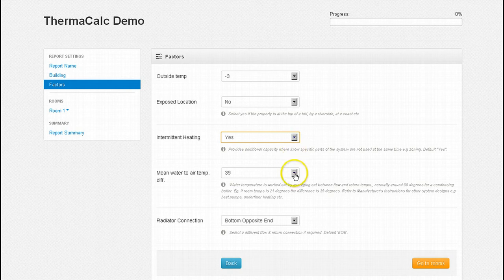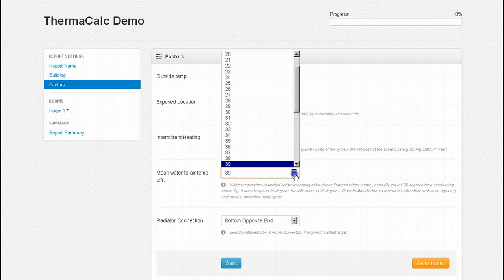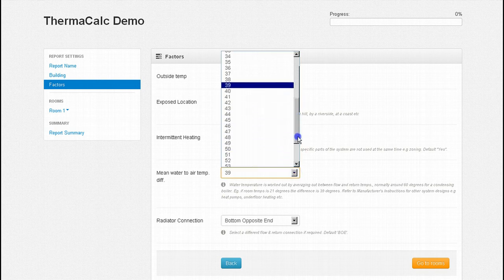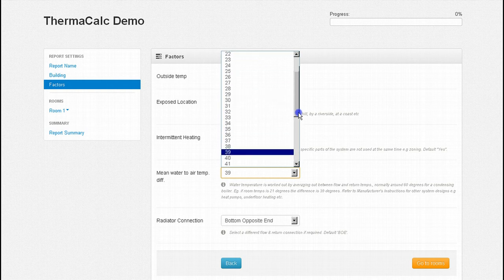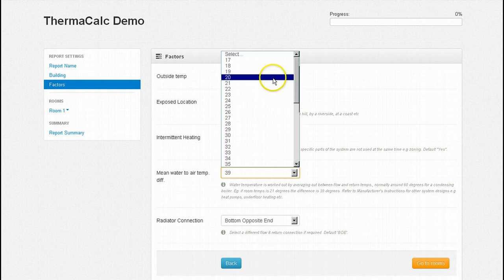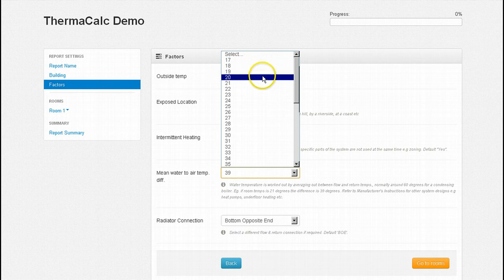Radiator temperature versus room temperature, known as the F1 factor, is simply the average temperature between the flow and return pipework minus the design room temperature. So if your flow and return average is 60 degrees and your room temperature is 21 degrees the result is 39 degrees. 39 is the default figure reflecting a common condensing boiler and radiator installation. You may wish to consider selecting a lower emission factor for heat pump and underfloor heating systems. If you are unsure about this, consult the manufacturer.